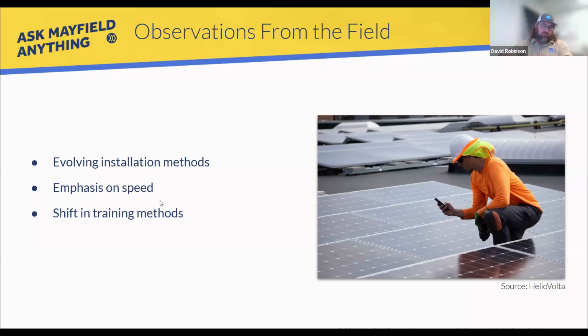So we were learning about how arc faults were actually being captured and detected. The interesting thing is, depending on the module and manufacturer, how they bond to ground would change the signal and could cause false arc faults, or reveal loose connections, which is actually a good thing. Arc faults, from a code standpoint, are good because they create safety and reduce the risk of systems failing. It does this very well, but you have to understand and work with manufacturers to figure out how they're actually capturing that signal, because that's huge and important in what we're running into today.